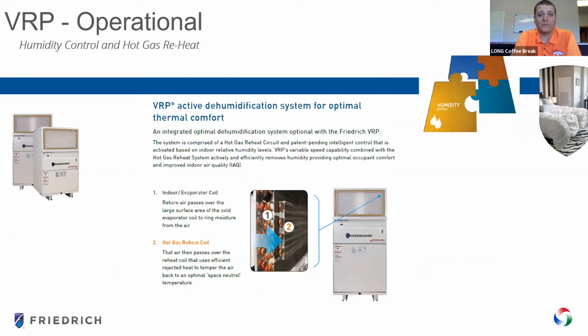And in Colorado, it's not always such a big deal, but one option that they do have if you're designing in a humid climate is that they have hot gas reheat available. So they'll be monitoring your return RH coming back to the system, and then based on whatever your set point is, heating that back, not overcooling your outside air, and then bringing it back up. So with their ability to monitor the RH of the system, they can more effectively use the modulating hot gas reheat circuit. Again, something we don't always see here in Colorado, but is available as a feature for this unit.